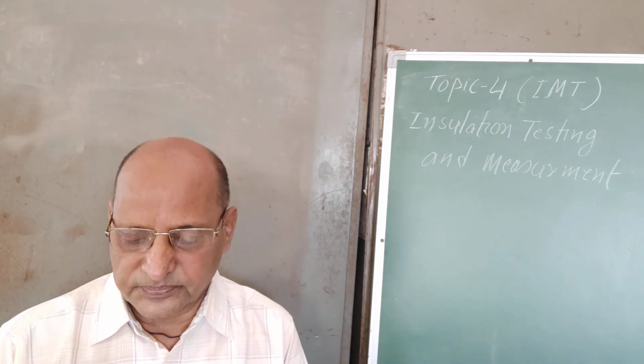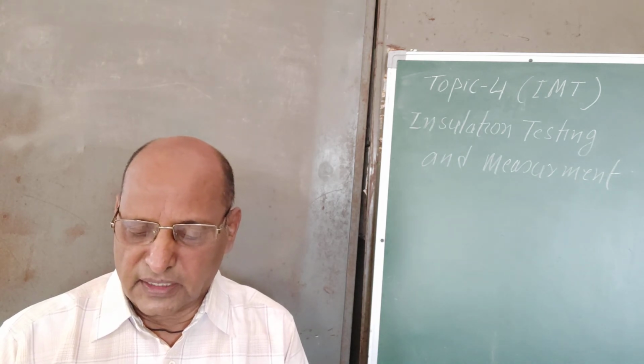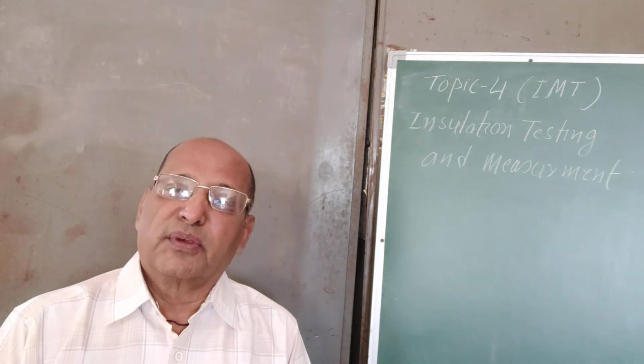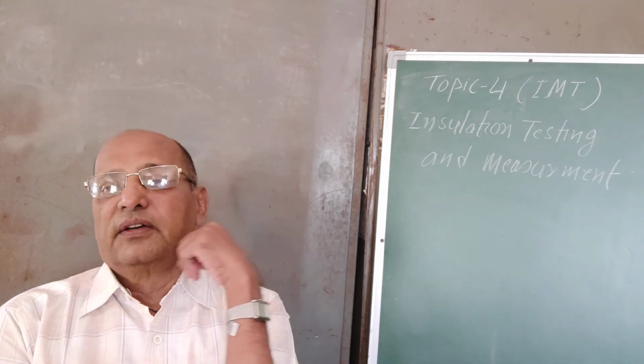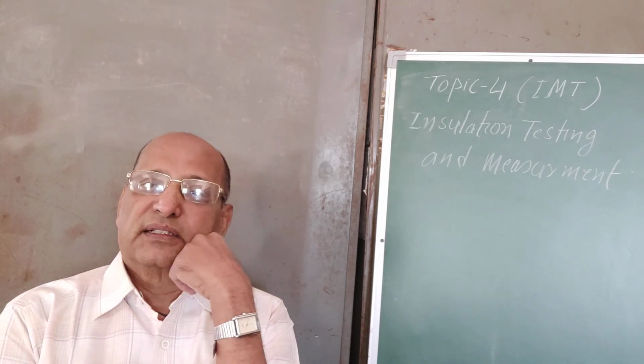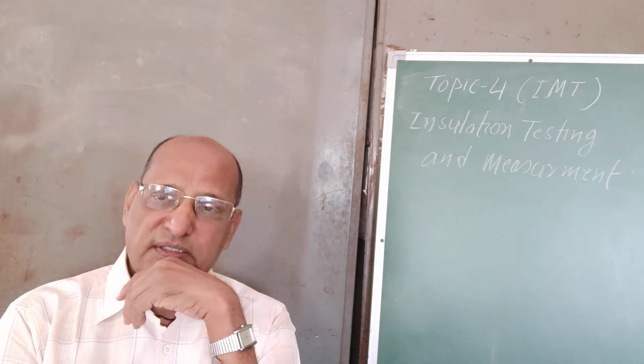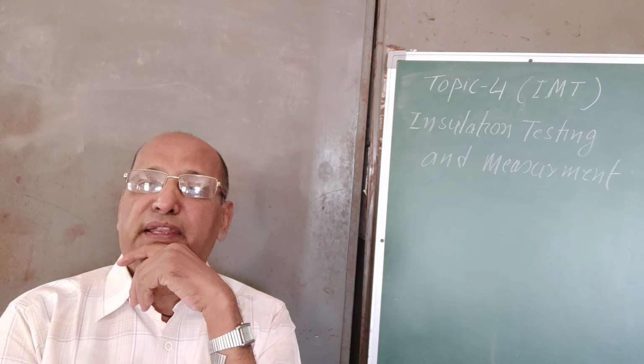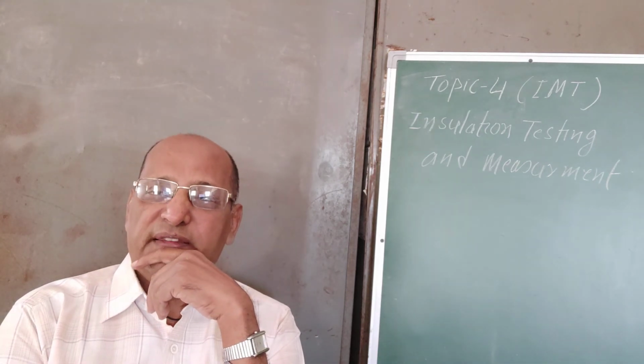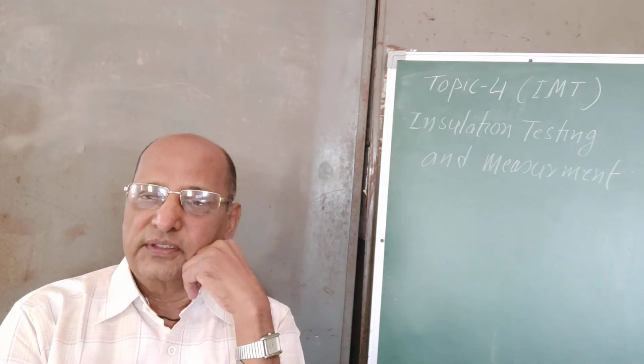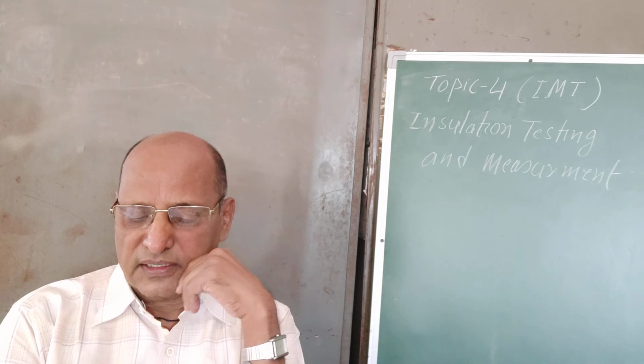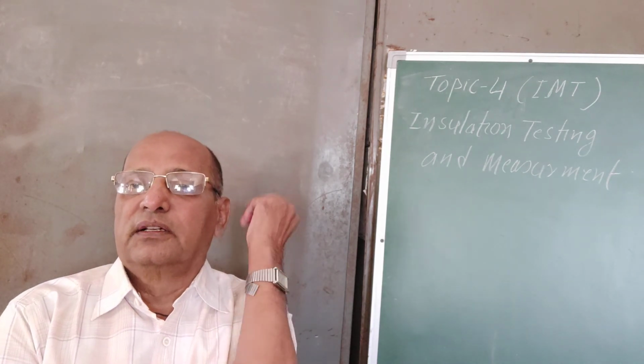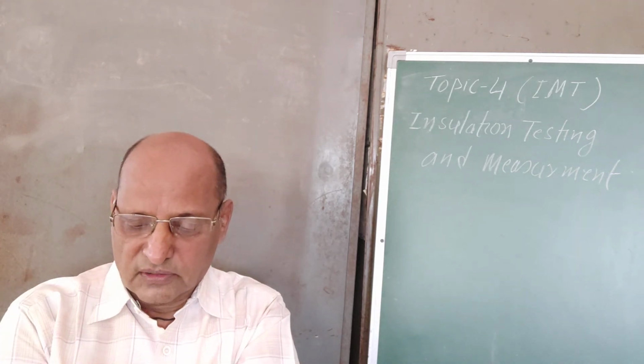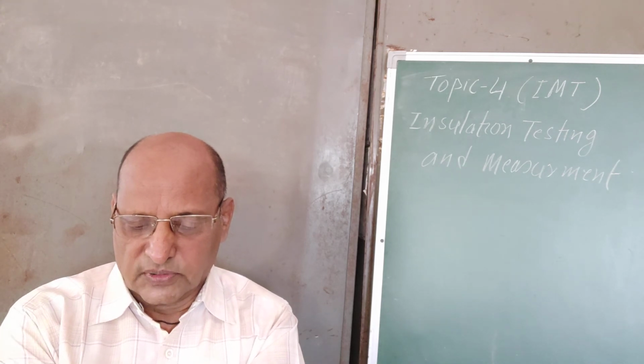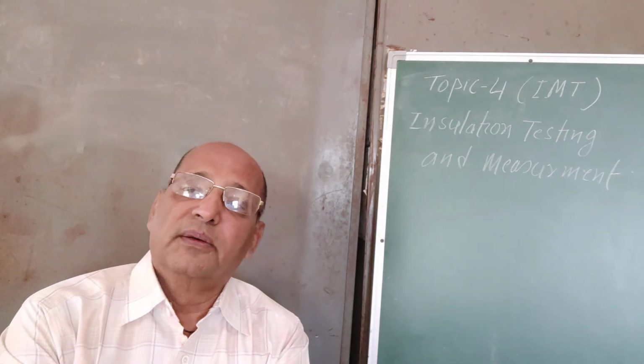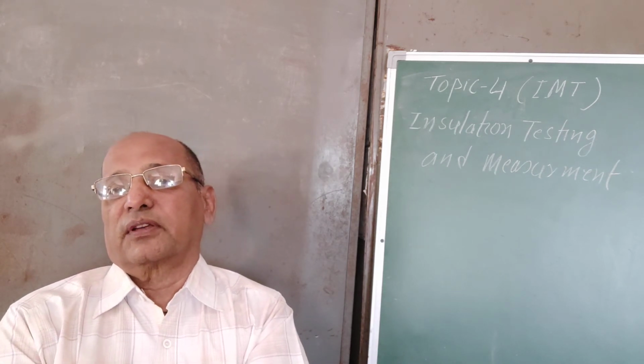They can ask what are the qualities of a good insulation. Then they can ask what are the instruments required for measurement of insulation resistance, then quality of insulation, then write the names of different insulating materials, then how you define dielectric strength of the oil, and what are the other properties of insulating oil. You have to write this down. Then they ask a question on the filtration of oil, how the filtration of oil is done for reclamation. So this question can also be prepared from this particular chapter. Then what are the methods of improving the insulation resistance of the oil.